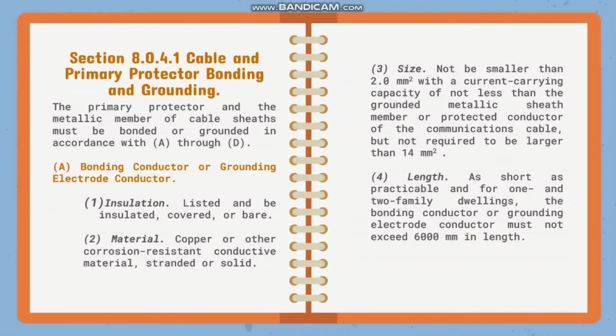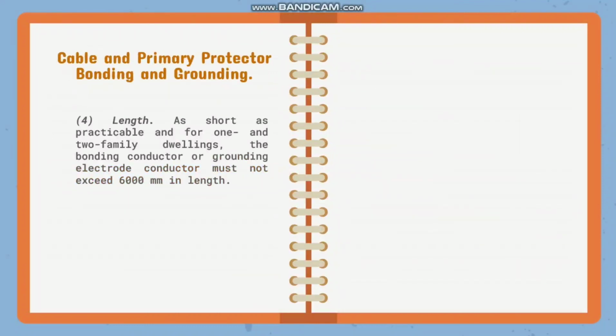For the length, as short as practicable, and for 1 and 2 family dwellings, the bonding conductor or grounding electrode conductor must not exceed 6,000 mm in length. So, the reason po kung bakit nililimitahan po yung length ng bonding conductor or grounding electrode conductor ay para malimitahan din po yung induced potential or voltage differences between the building's power and communication systems during lightning events.